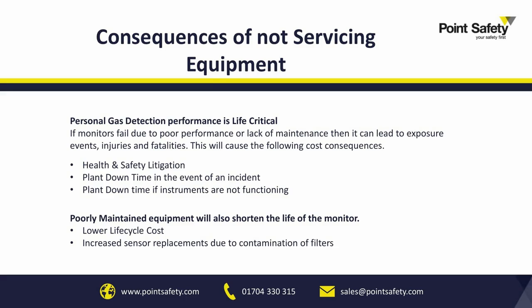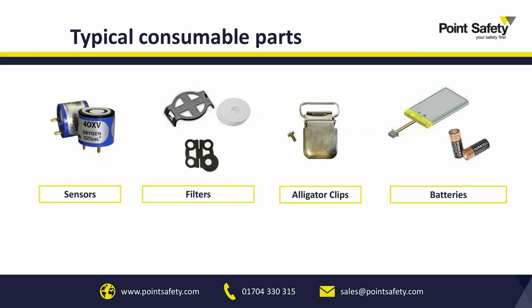Contamination of the filters, the drift that we've talked about on sensors, will lead to poor servicing, will lead to increased or decreased periods for sensors, so increasing that lifetime cost of the monitor. So in all service applications, there's a few typical parts that are generally replaced more often from a service point of view. So again, the sensors we've talked about there with their life expectancies, you would try and replace these prior to them failing and in line with their expected life.